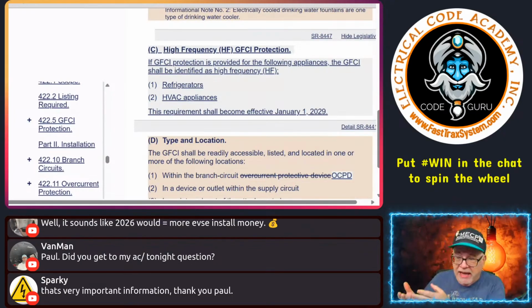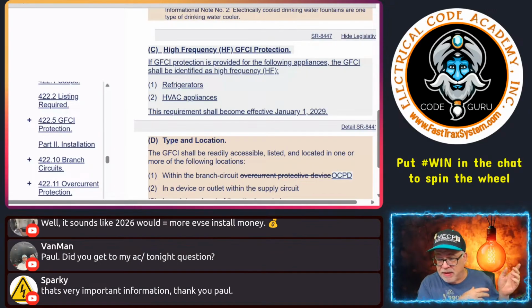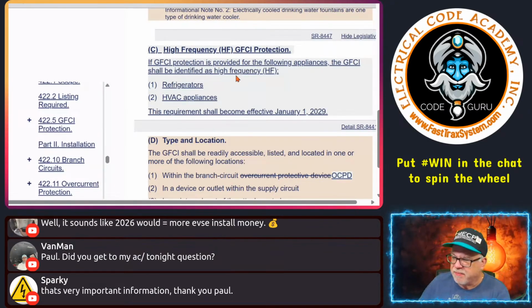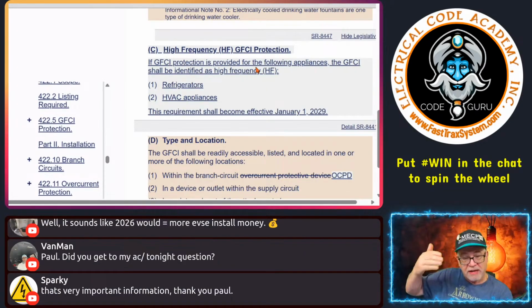We were okay with January 1st, 2029, but they were not. They wanted to stop at September 1st, 2026. So we're saying that for refrigerators and HVACs you have to use a GFCI that's marked high frequency, because that's where their issue is.